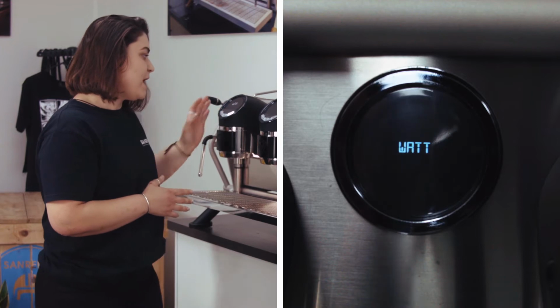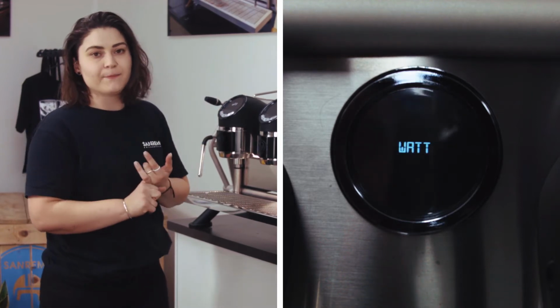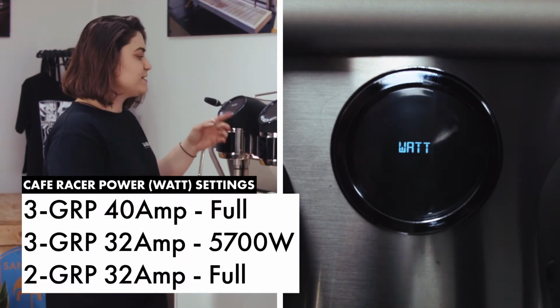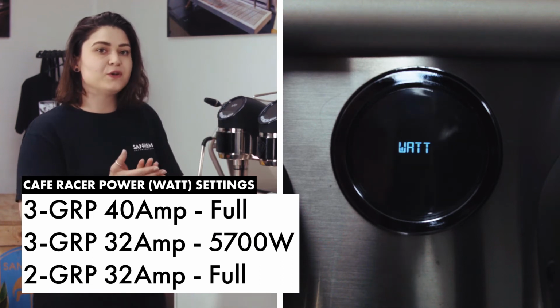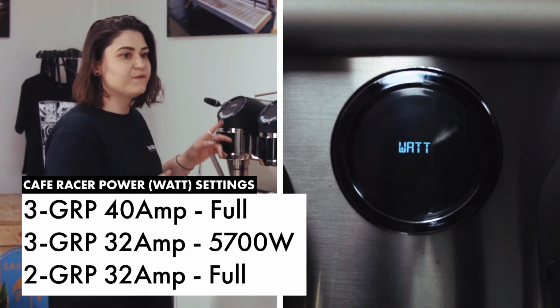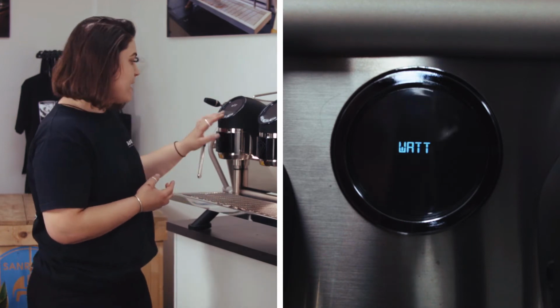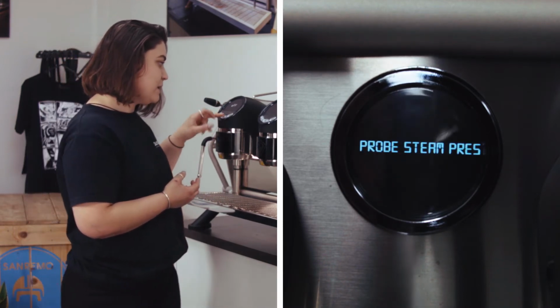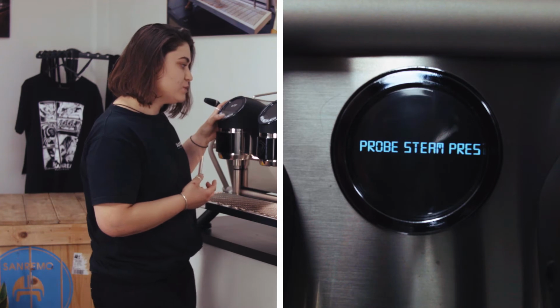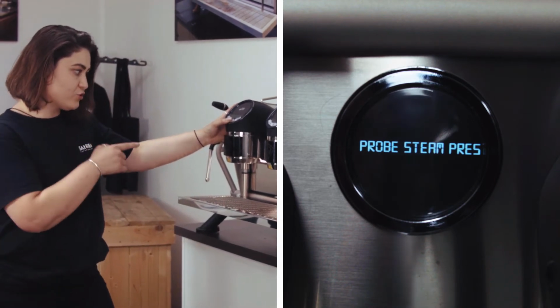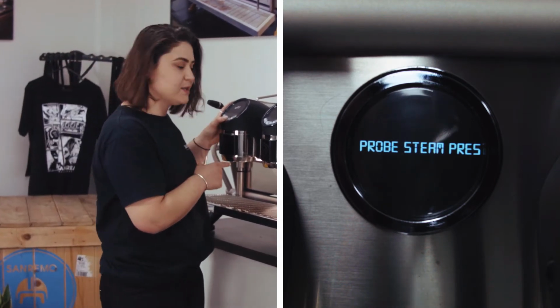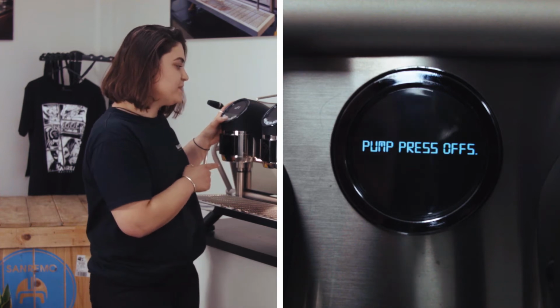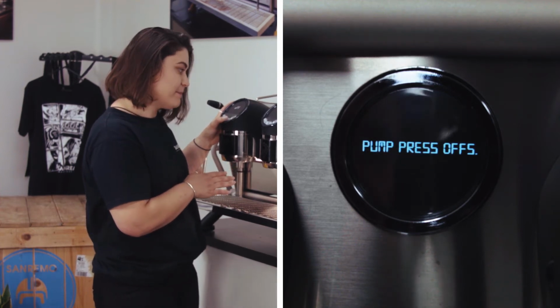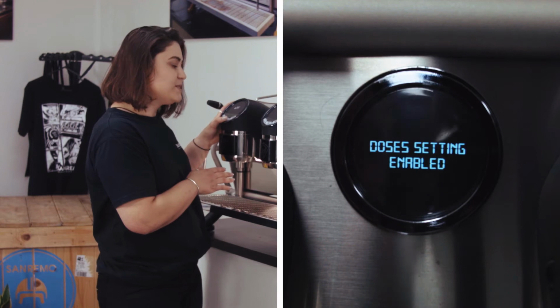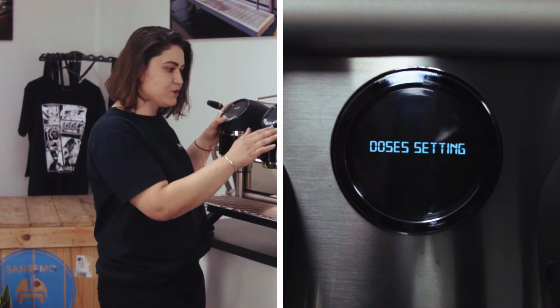Enter. Watts. If you have a 40 amp Cafe Racer, the watts will be set to full. If you have a 32 amp racer, the watts will be set to 5,700 watts. Once that's done, enter again. Probe steam pressure enabled, so that your pressure transducer at the back on your steam boiler, make sure that's enabled. Pump offsets 0.8, leave it as is. This comes from factory.